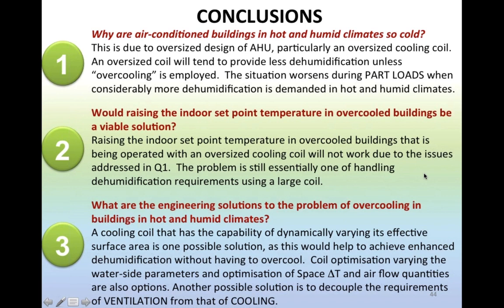That is yet another talk that I have, and some work that we've done in our group, where we separate the ventilation requirements, handle the high humidity loads through a separate heat mass transfer process, and then we provide the sensible cooling through another different track. And that combination also provides tremendous advantages, both in terms of individual zone level ventilation control, demand ventilation control, and provides a much better overall performance.